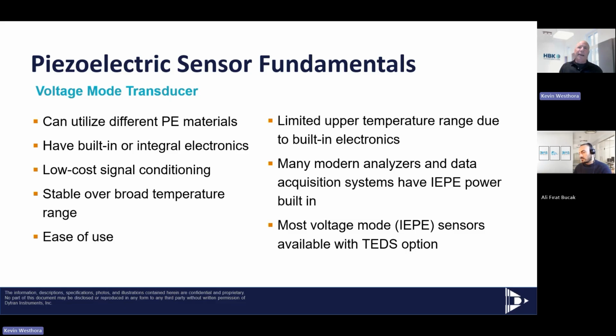I cannot use ceramic, for example, in a charge mode accelerometer. But in a voltage mode accelerometer, I can use any crystal. So I can use quartz, I can use ceramic, I can use other bismuth titanate. It has the electronics built in. It's stable over a pretty broad range. Typically, we quote our voltage mode sensors from -40 to 165C, so pretty broad.